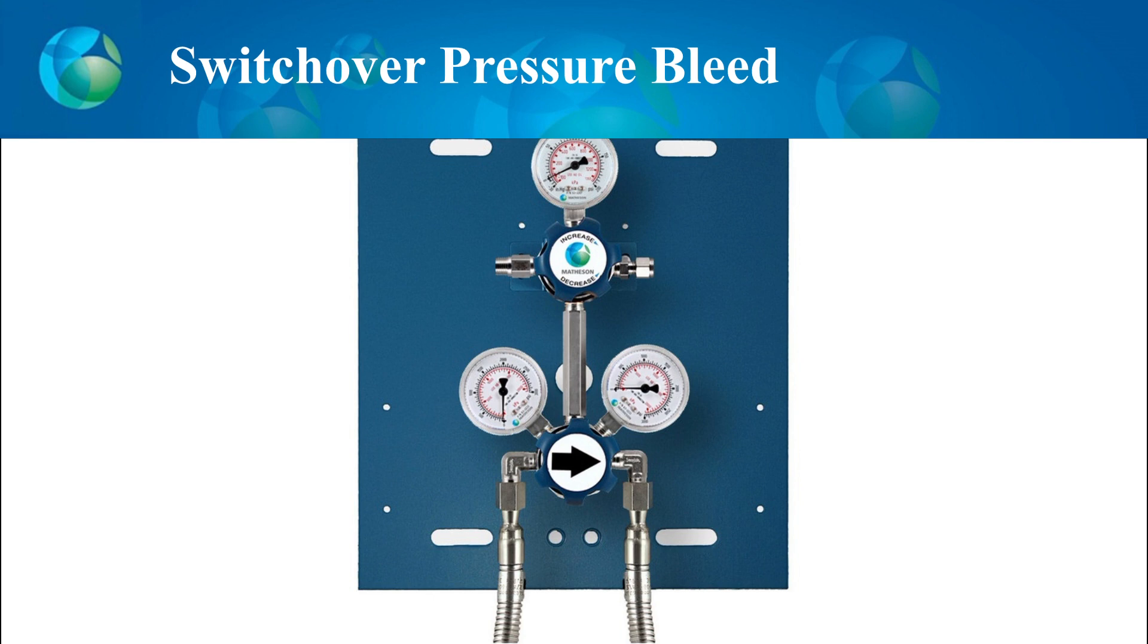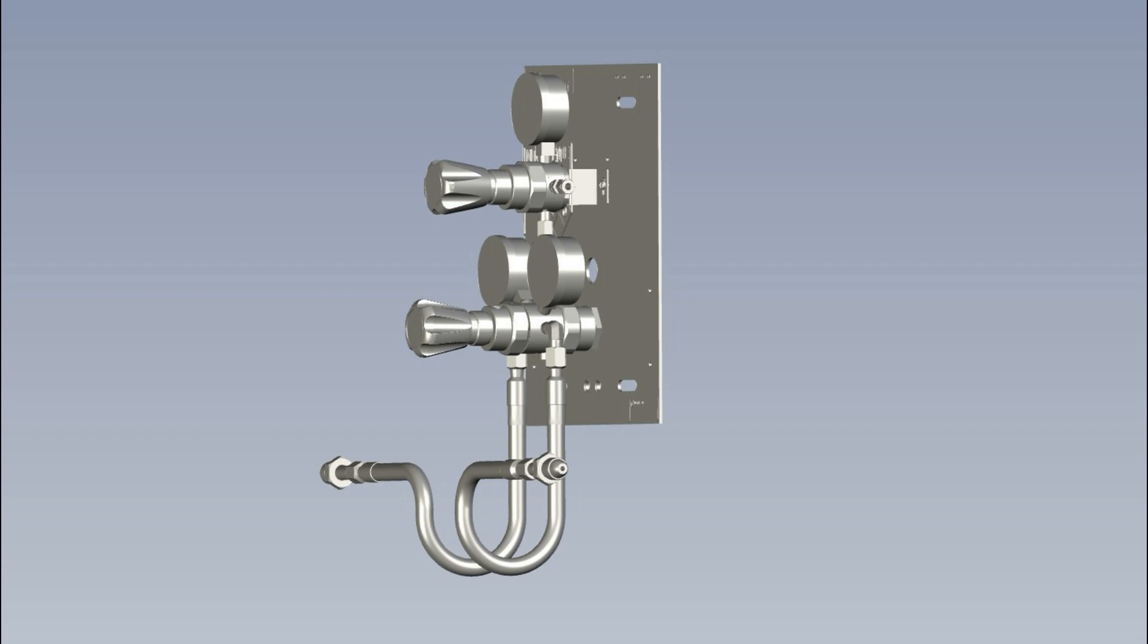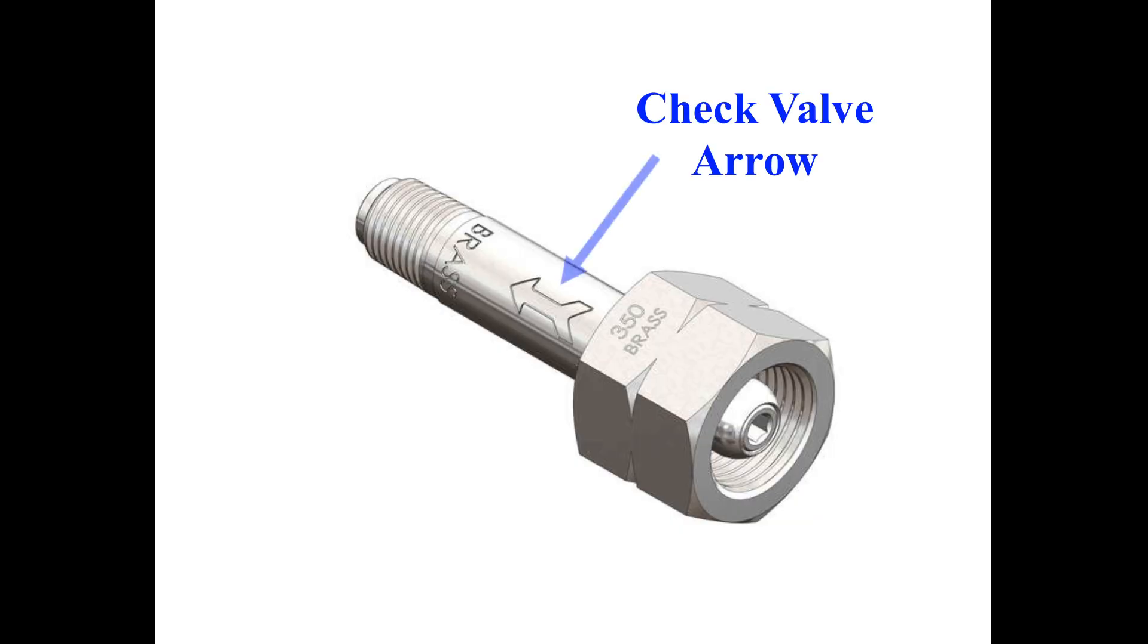Switchover bleed is a normal occurrence. The switchover system is safe and gas will not bleed from the full cylinders on one side into the empty cylinders on the other side. Both flex hoses in this switchover, and almost all switchover systems, have CGA connections with integral check valves which will prevent backflow into the cylinders.